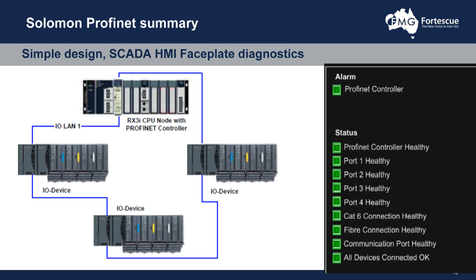Our PROFINET infrastructure and communications networks were centralized on a ring format, and early on in the scope of the works we were able to define a lot of our SCADA interfaces using the standard diagnostics available with the PROFINET scanner and controller in the GE architecture. We grabbed that information into a centralized format and displayed it on standard class object faceplates. This kind of information now underpins our process control networks, and the value is immeasurable.